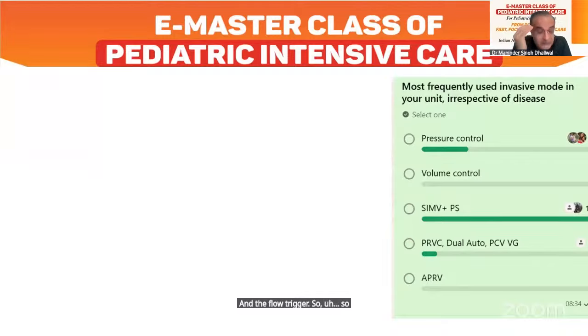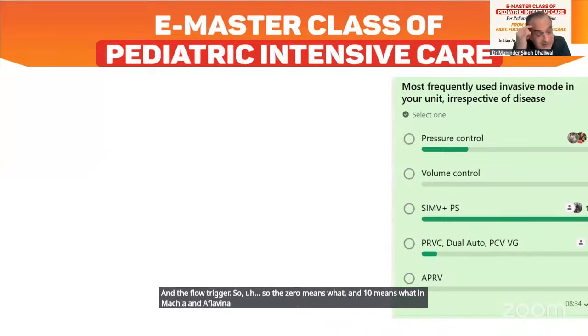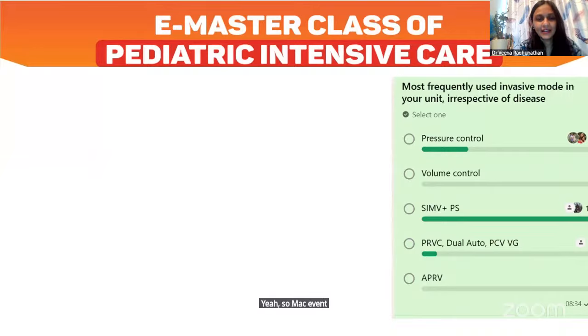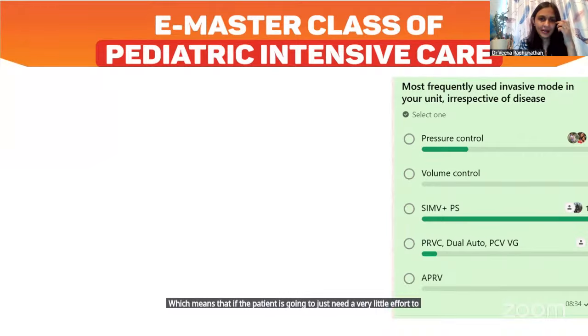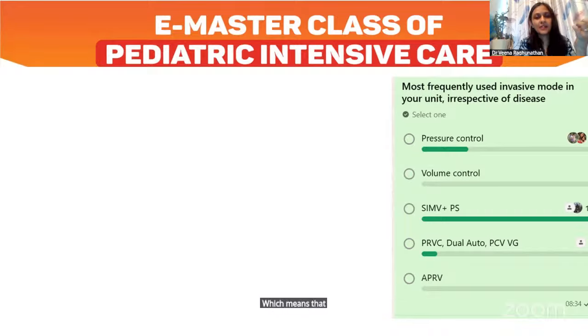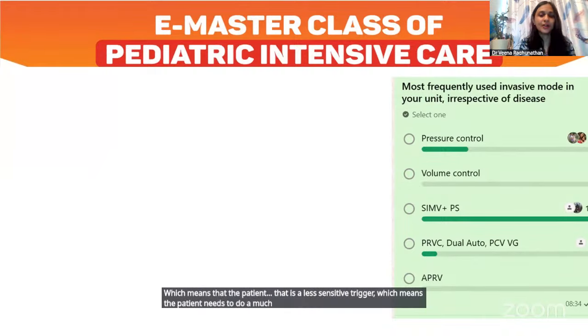So what does 0 mean and what does 10 mean in Maquet? I'll ask Dr. Veena, because we recently had a doubt regarding this. On the Maquet ventilator, the flow trigger, if we set it at 10, means a very sensitive trigger, so the patient needs just a very little effort to trigger the breath. As against that, if we set a flow of 1 or 2, that is a less sensitive trigger, which means the patient needs to make much more effort to trigger the breath.